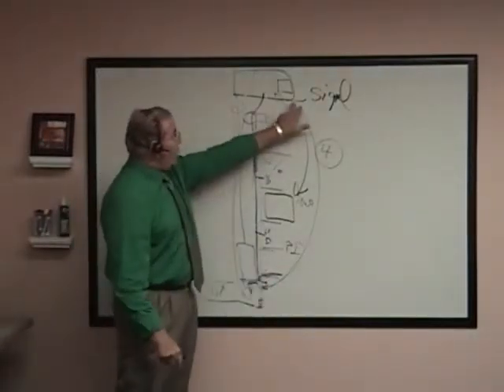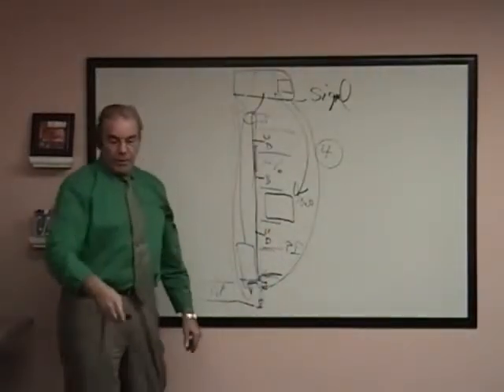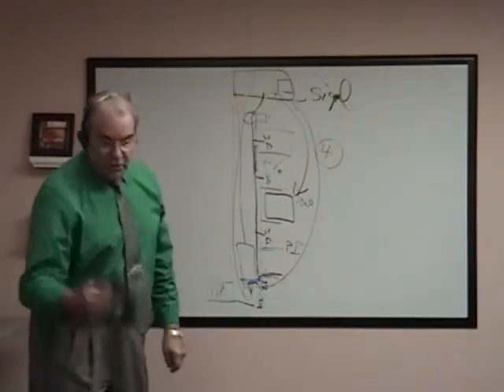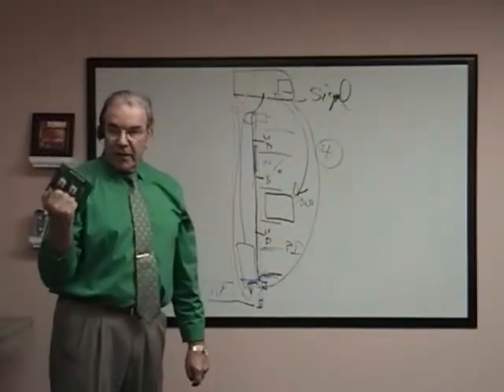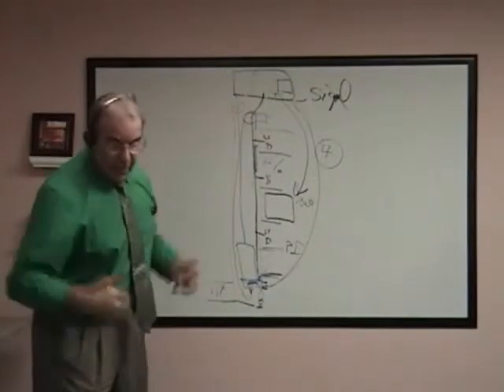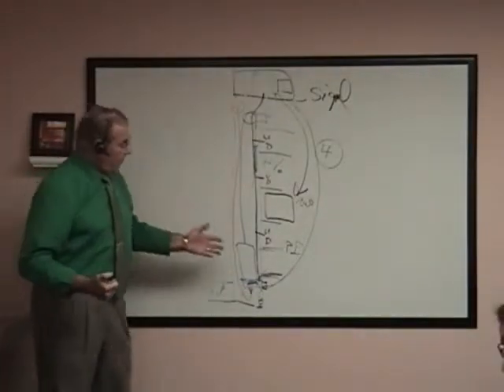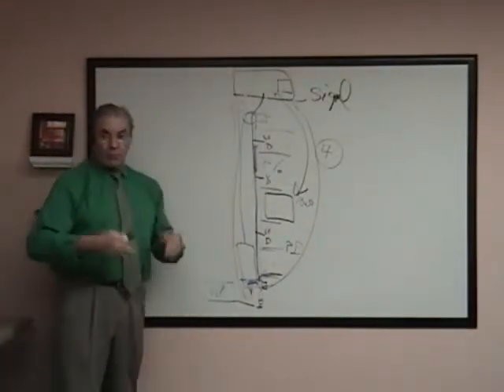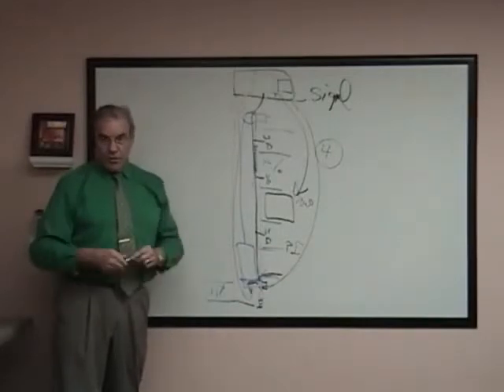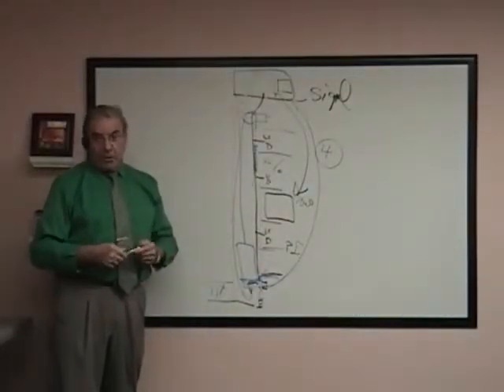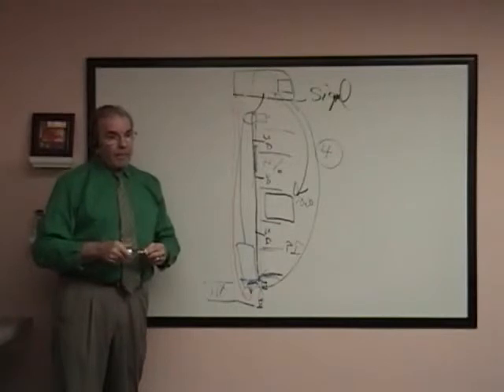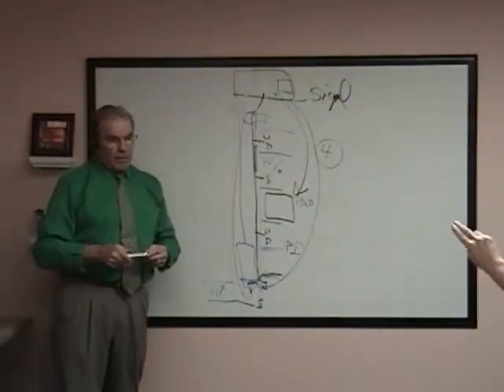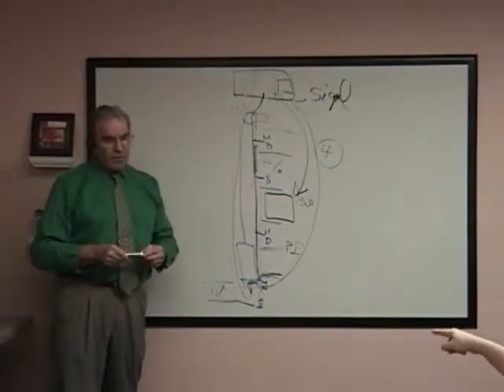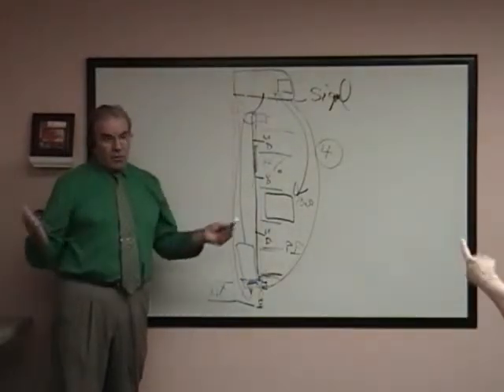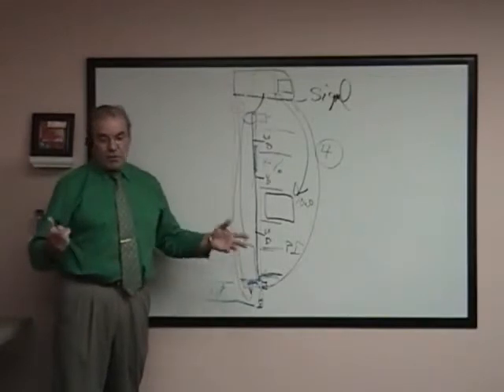Then they only need 2 wires to come back up to trip the controller device during the event. So depending on how we design it, it depends on how many actual hatch wires they need. We tell people 4 because that's the worst scenario, but it could be 2. You see the prints and go, oh, you only need 2, and there might already be 2 spares available. That saves a couple hours of install. If they can just pick up the 2 wires here, this is a very simple install.